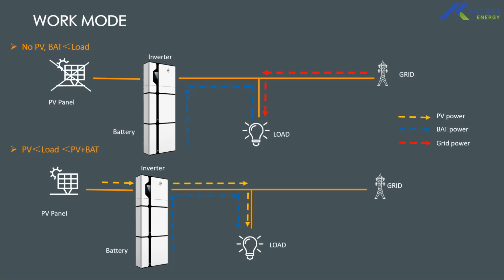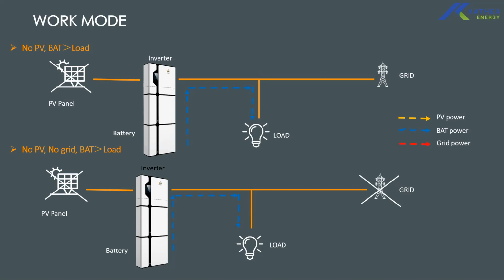When the PV is less than the load, and the PV and the battery together can cover the load, that's a scenario where your battery can supply your loads along with the PV. So you'd get all of your PV pushed to the load, and then if there is a deficiency, it's taken from the battery to supplement the load. And then if you don't have grid and you don't have PV, that is a load shedding scenario at night, you get your battery supplying your loads. That is only your critical loads connected on the backup port.